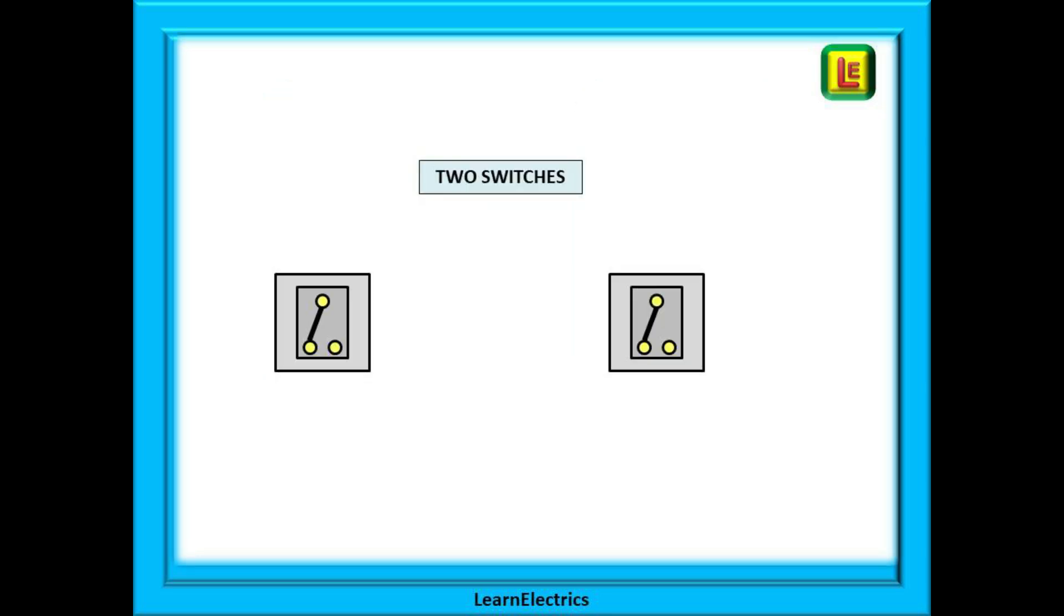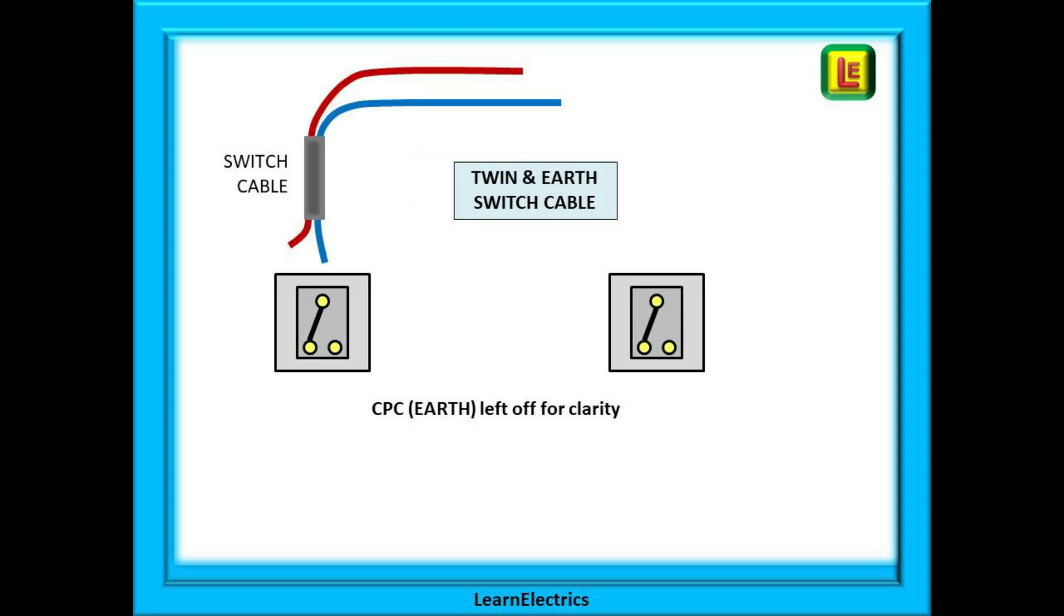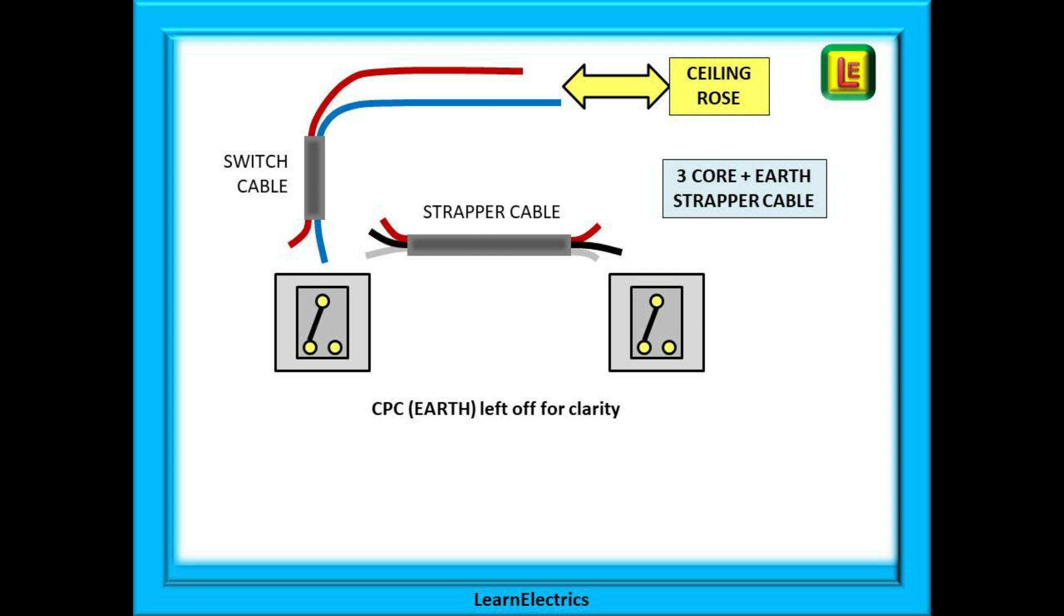We can begin with our two switches. One switch may already be in position and you may be adding a second to convert one-way to two-way, and the process is just the same. We have our twin and earth switch cable and this comes from the ceiling rose. Next we have the three core strapper cable that links the two switches. This link cannot be made with a standard twin and earth cable, and the CPC should not be used as a live wire.